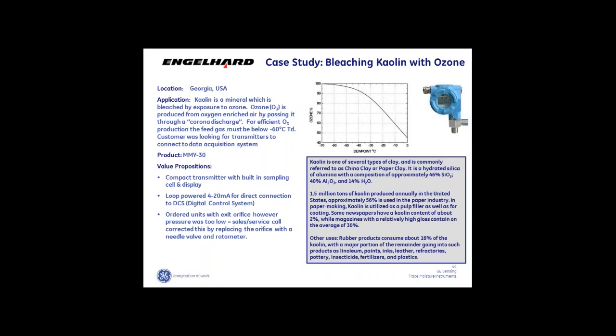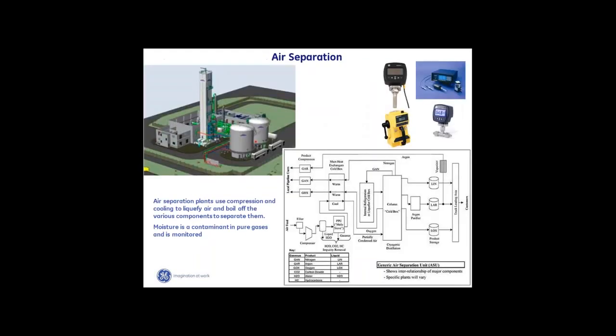Another big application for us is air separation, where we can get pure gases — mainly nitrogen, argon, and oxygen — from separating them out of air. Air is a mixture of gases, and this is sort of the reverse of distillation. In distillation we start with a liquid, heat it, and separate components at different temperatures. Here we start with gases and as we chill them down to very low temperatures, nitrogen, argon, oxygen, and CO2 separate at different temperatures. We have to make sure we remove all of the water, or ice will form on our cold box or in our cryogenic heat exchanger.